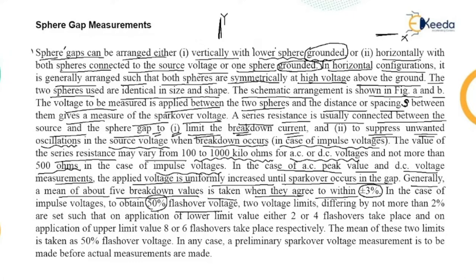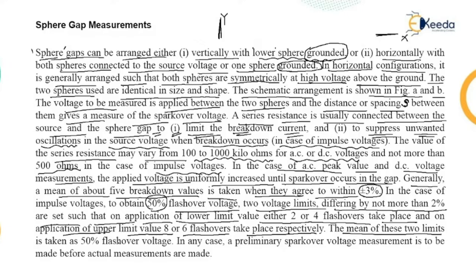Generally a mean of about five breakdown values is taken when they agree to within plus or minus three percent. In case of impulse voltage, to obtain 50 percent flash over voltage, two voltage limits differing by not more than two percent are set such that on application of the lower limit, two or four flash overs take place, and on application of the upper limit, eight or six flash overs take place respectively. The mean of these two limits is taken as 50 percent flash over voltage.